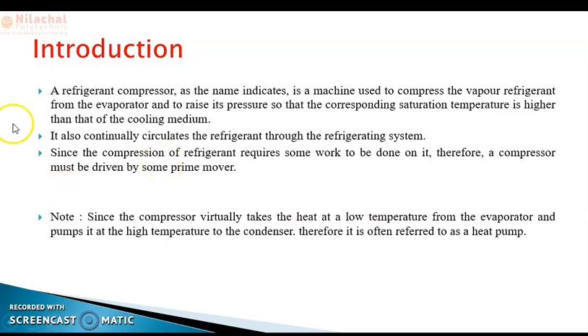As the name indicates, the refrigerant compressor compresses the vapor refrigerant from the evaporator to raise the pressure, so that the corresponding saturation temperature is higher than that of the cooling medium. Generally in the refrigerant compressor, you are compressing the low-pressure refrigerant from the evaporator to high pressure to the condenser, and the refrigerant continuously circulates through the refrigerant system. Since some work is done on it, the compressor must be driven by some prime mover.